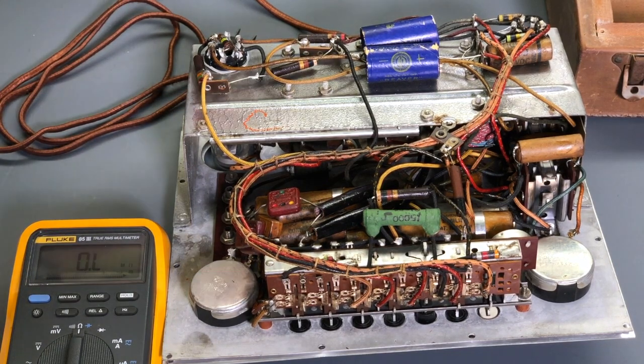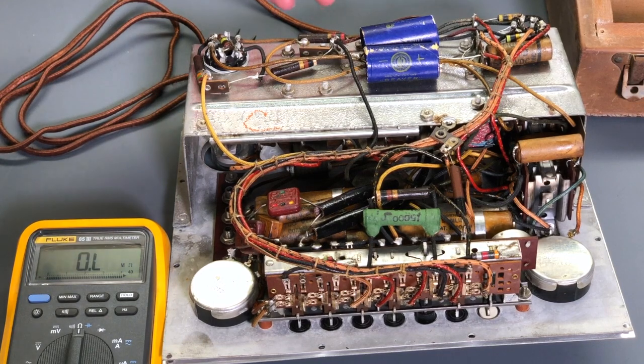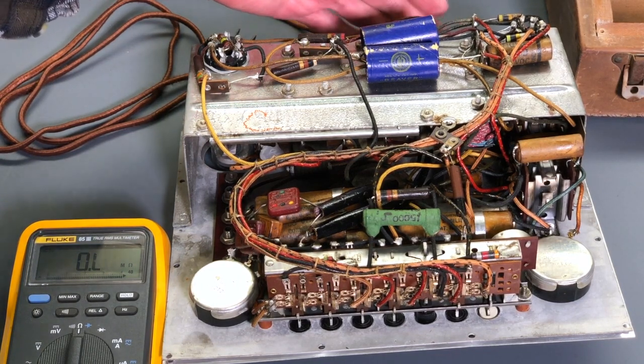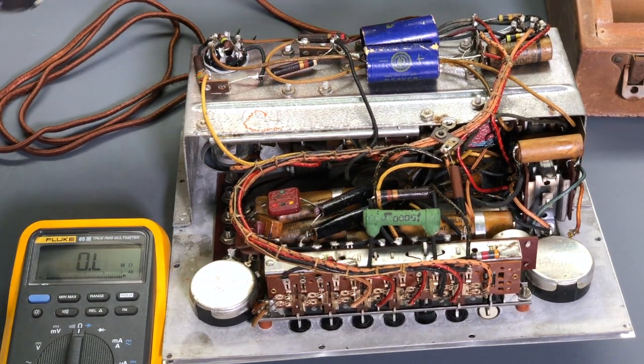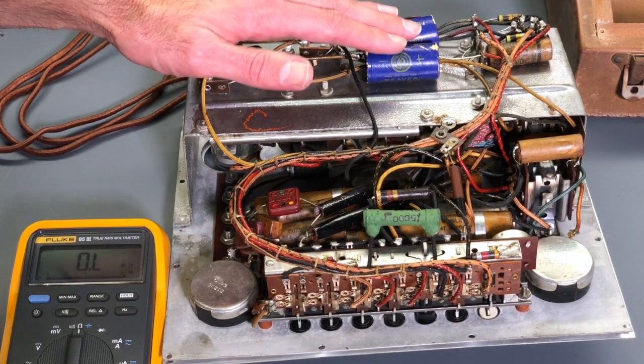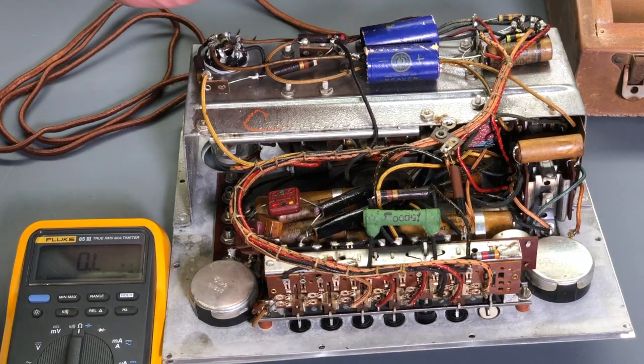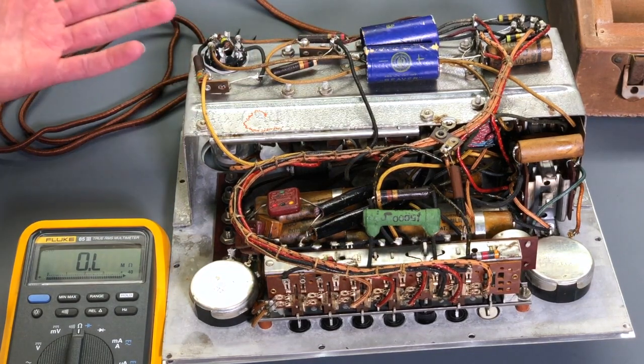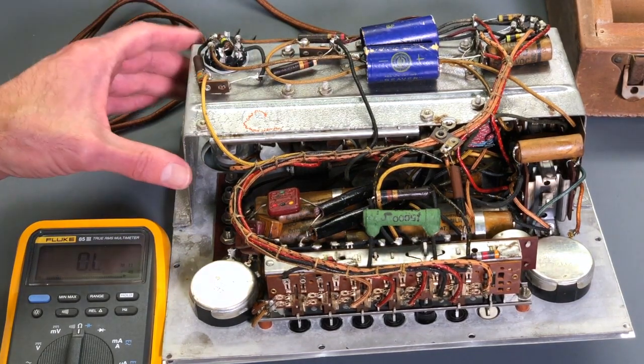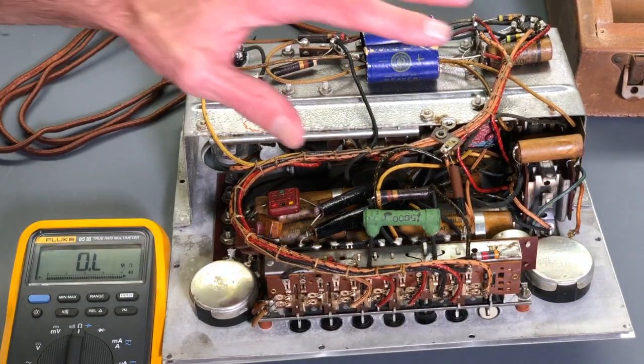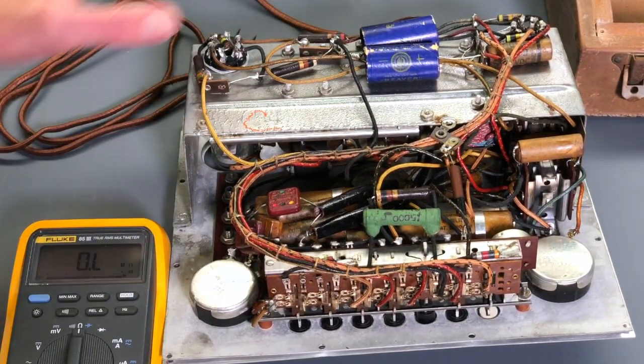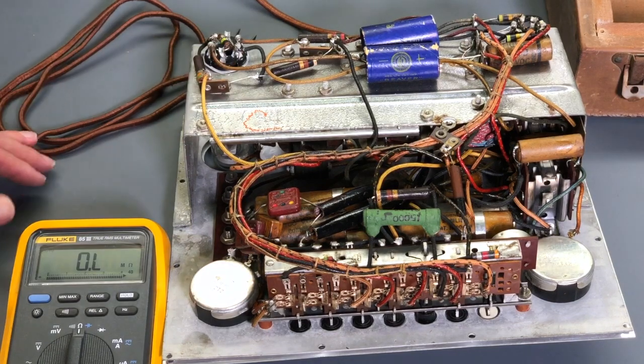So the next step is to apply some AC, and we want to see if the transformer is functioning okay, and also if the tubes turn on and start to produce a little bit of DC. Now these capacitors, we'll definitely need to be changing these out before we put full voltage to the unit, but I want to see if the transformer is functioning and just see if a little bit of activity occurs in the circuit. So we'll do that next.